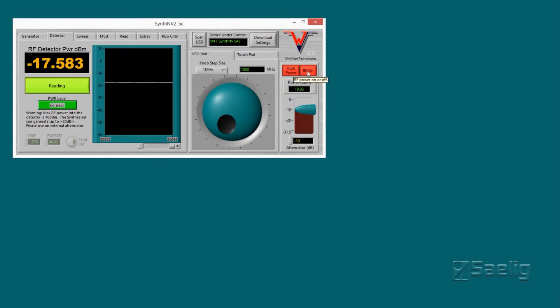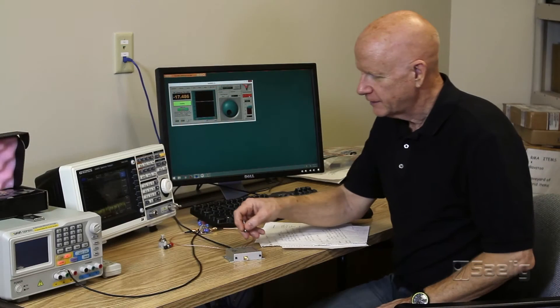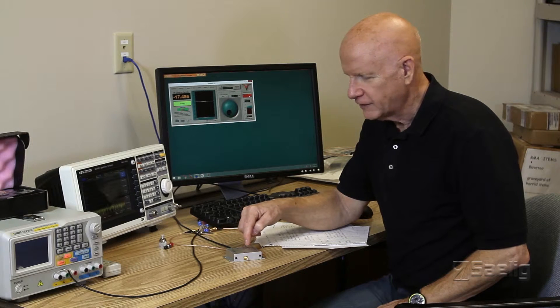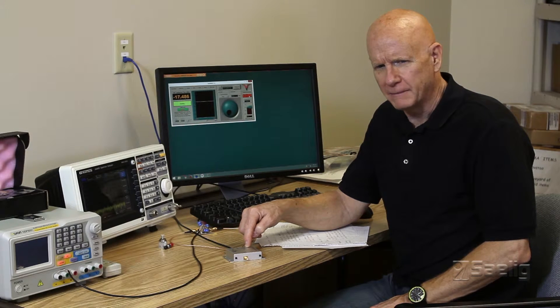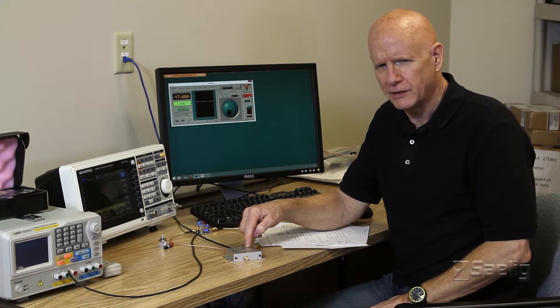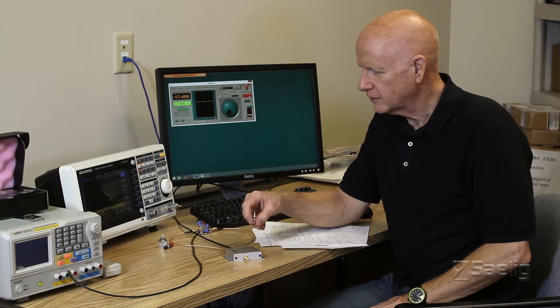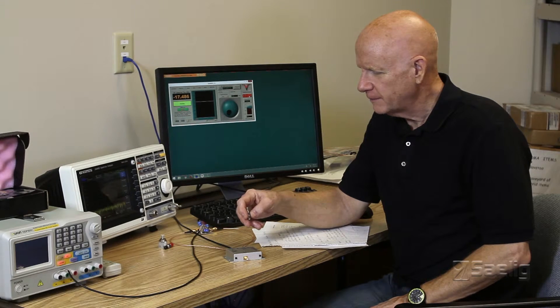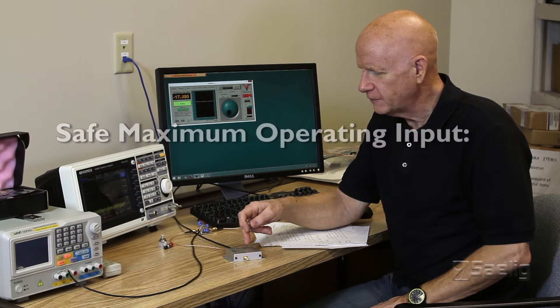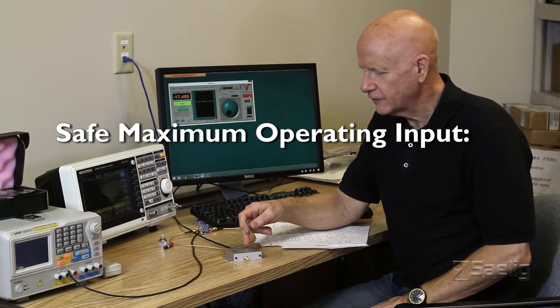One thing I should mention is that the RF detector input can be damaged if you put too much energy into it, too much power. The safe maximum operating input for this is plus 10 dBm, and it can be damaged if you go higher than that.